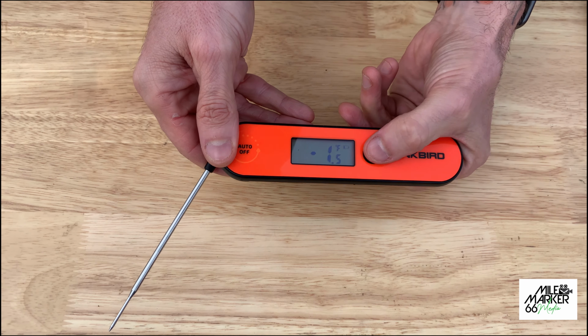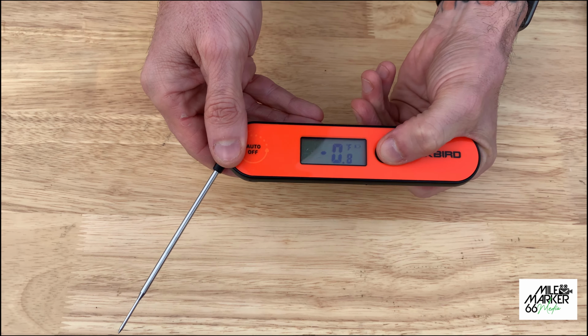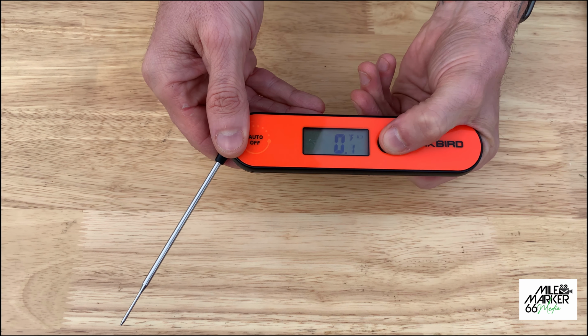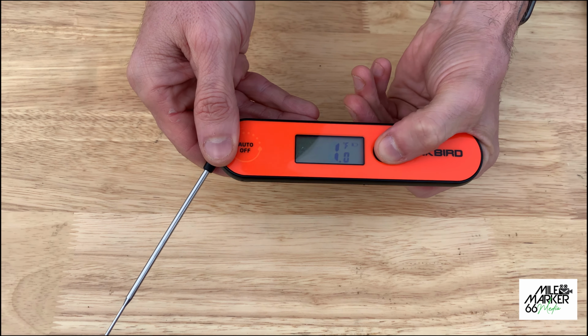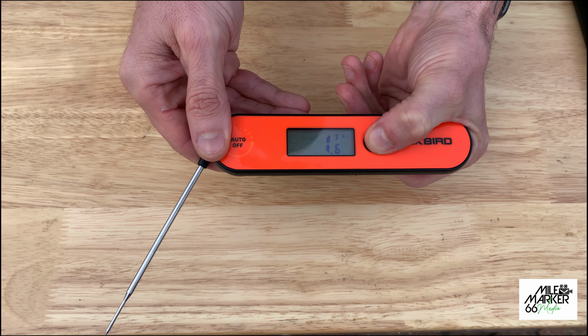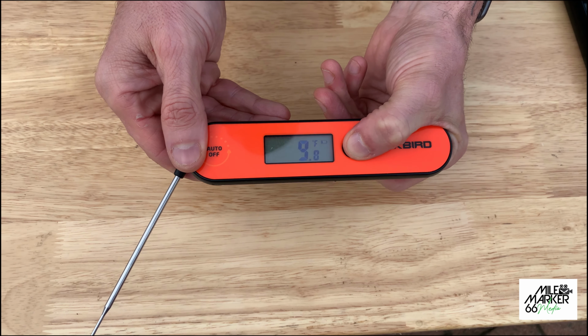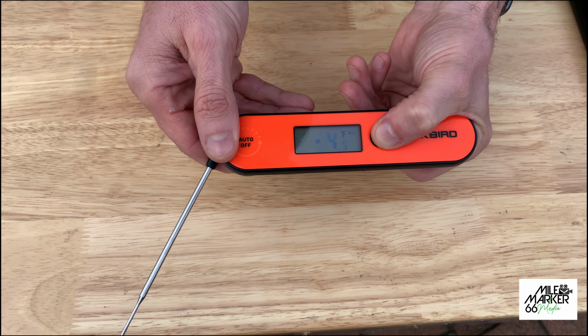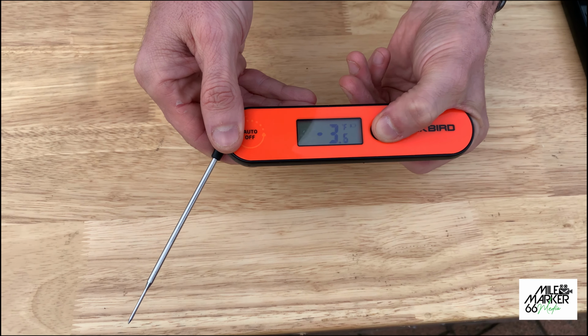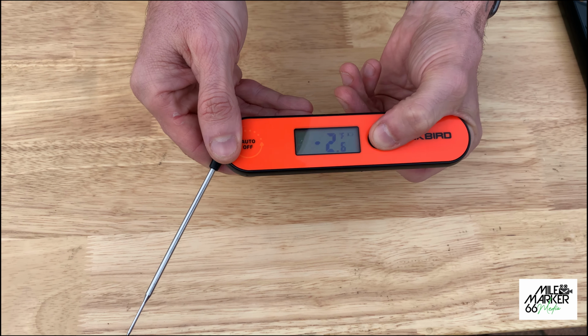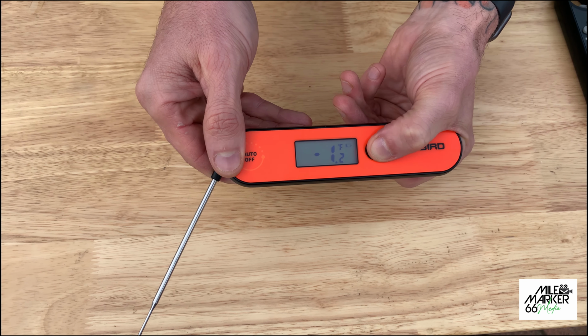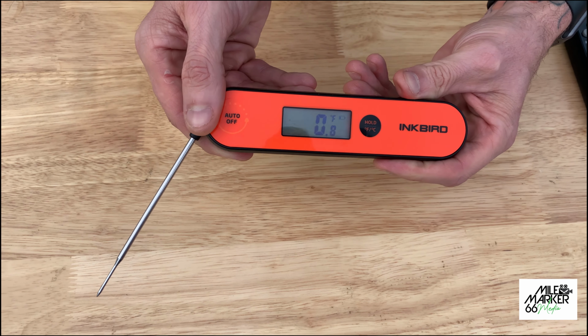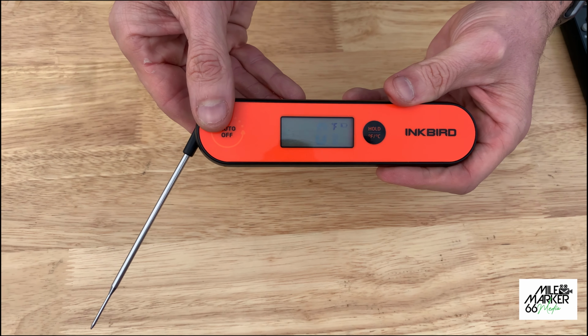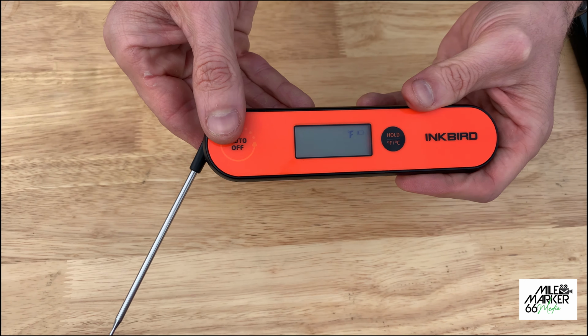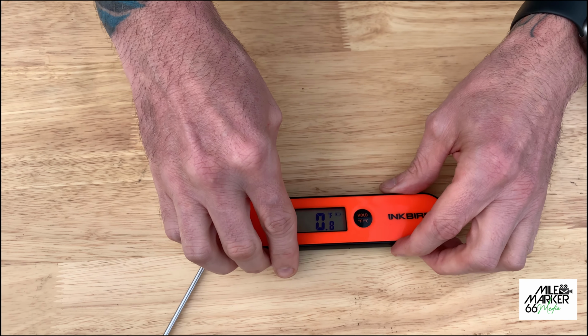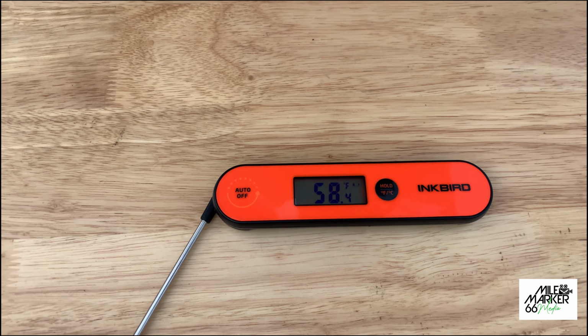What this is going to do is cycle through from plus 5 degrees Fahrenheit to minus 5 degrees Fahrenheit. You can click it once to tick them over individually, or you can hold the button down, and it'll just speed up cycling through. So we know that we were under by 0.8 of a degree, so we want to add 0.8 of a degree. And this is where it can get a little tricky or confusing. So now we have 0.8 degrees Fahrenheit displayed there, and that's how much we were under by. So if I lay this flat down now for 10 seconds, that will set that calibration.